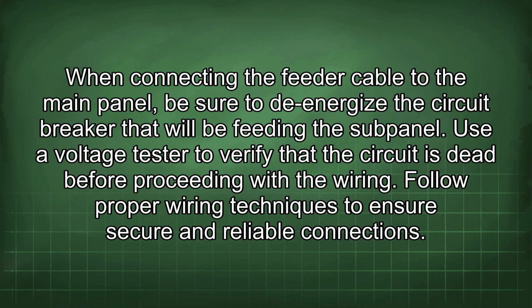When connecting the feeder cable to the main panel, be sure to de-energize the circuit breaker that will be feeding the subpanel. Use a voltage tester to verify that the circuit is dead before proceeding with the wiring. Follow proper wiring techniques to ensure secure and reliable connections.